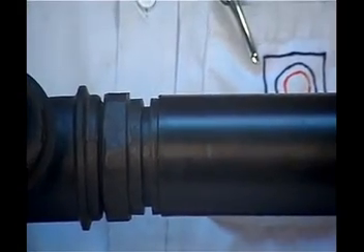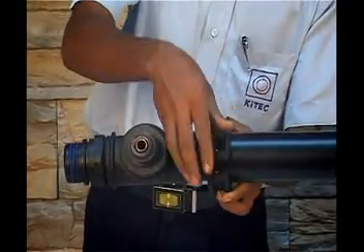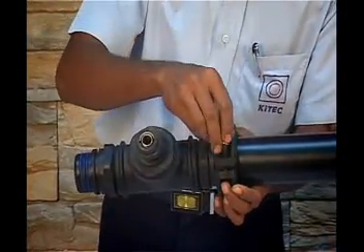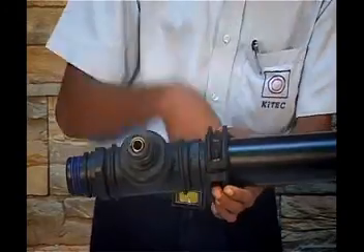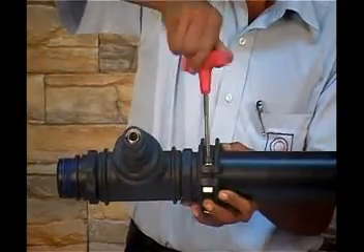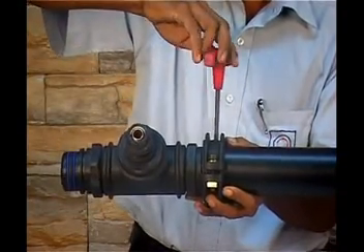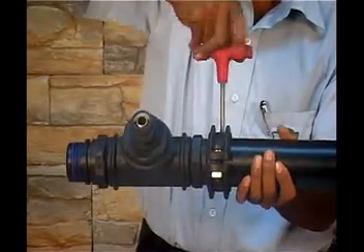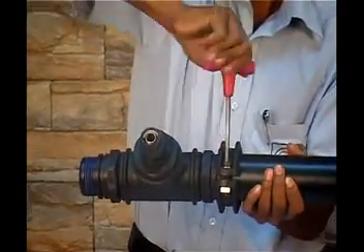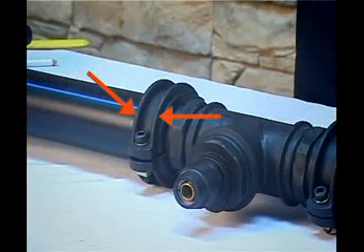After inserting the inner part of the fitting, both the clamp halves are placed, ensuring proper alignment with the steps provided on the inner part of the fitting. After placing the clamp halves in place, the Allen screws are tightened fully. The sealing is on ID of pipe. When the Allen bolts are tightened, the pipe gets compressed by the clamp. This leads to compression of O-rings, leading to positive sealing. The clamp holds the joint in position.